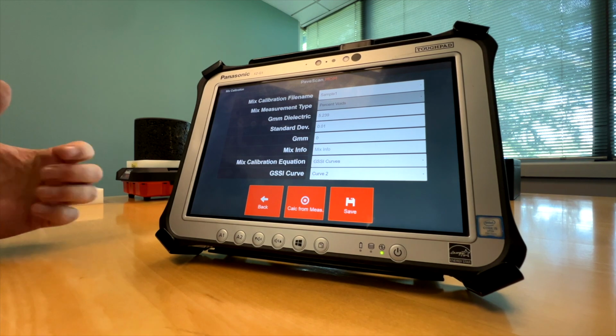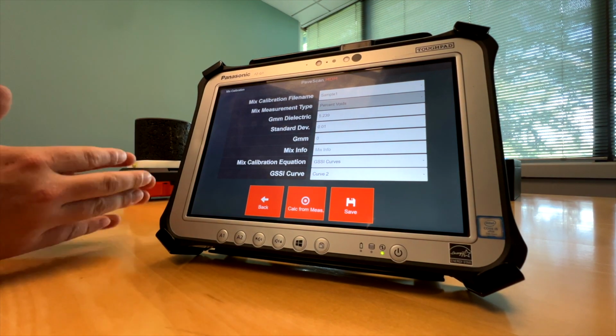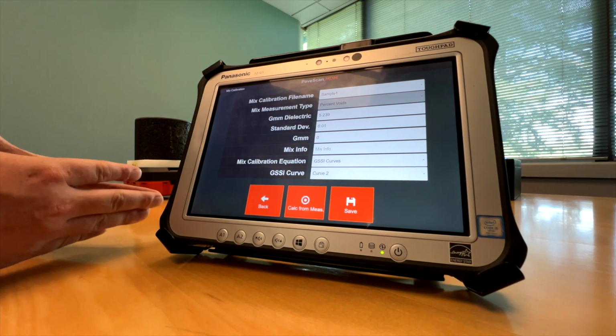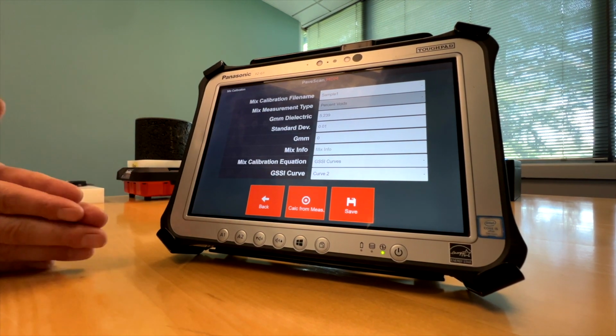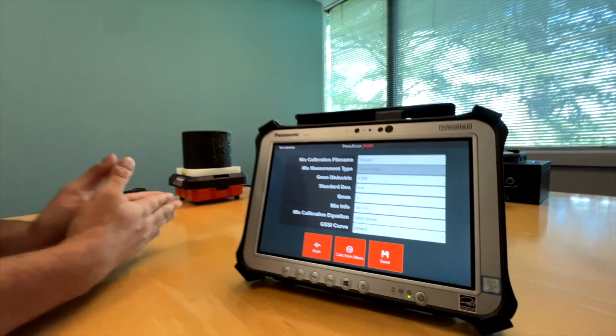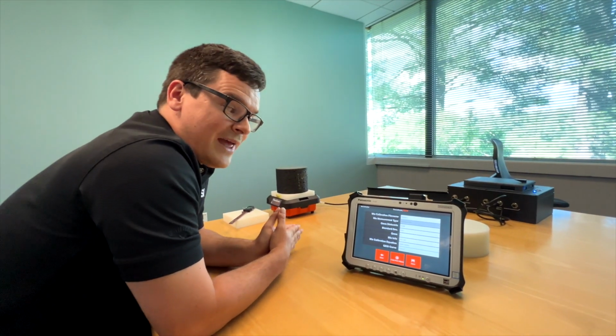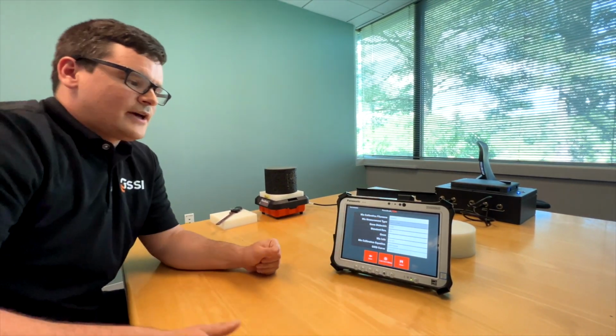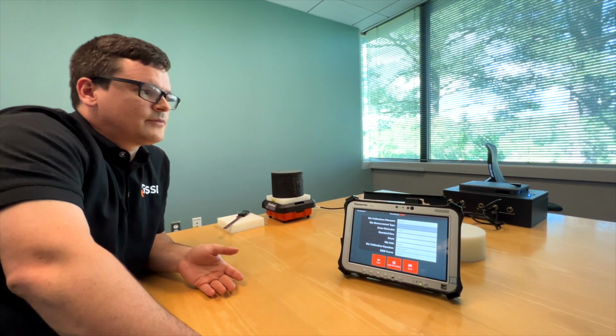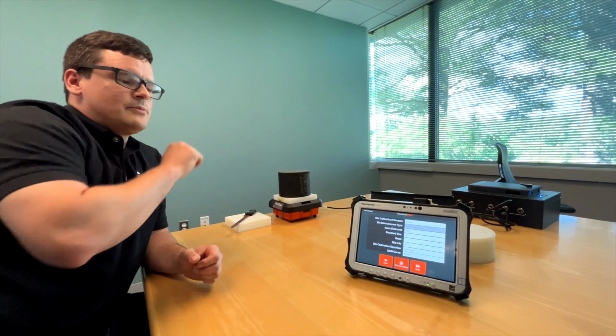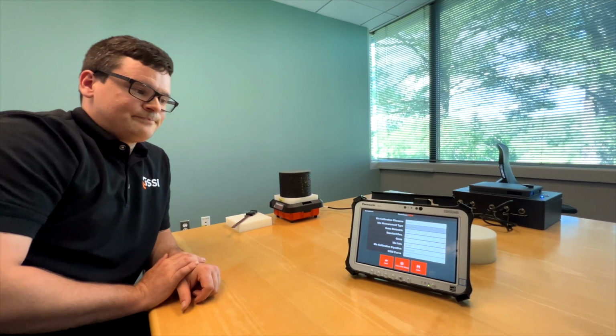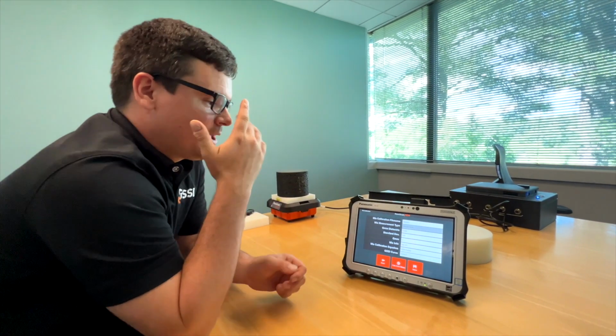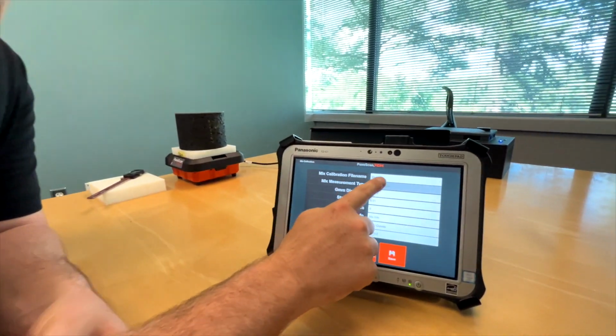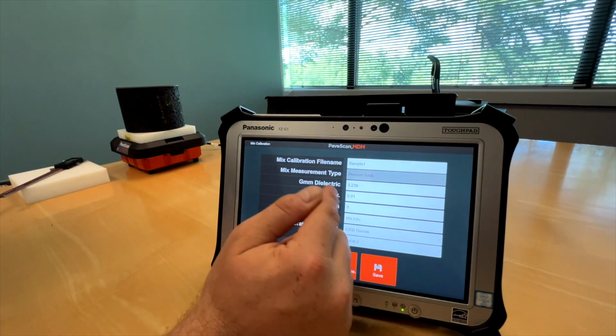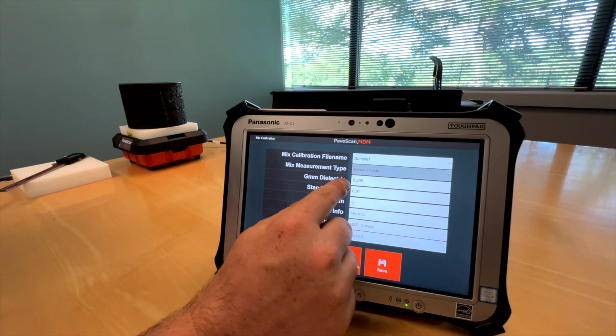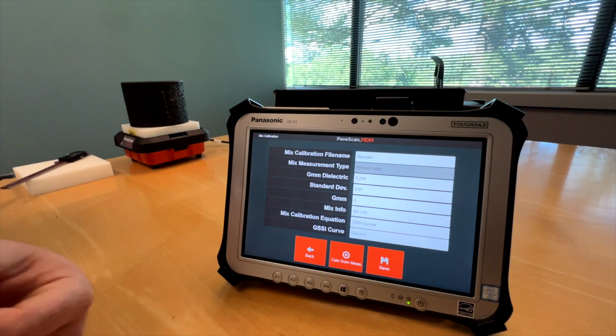Okay. So now I have created a calibration file. I've created a calibration that is linking the percent void, how much air is in a sample, to the dielectric of the sample itself. So now what I can do is I can take that value, 5.239, and if I have something like a PaveScan, I can create a mixed calibration now on the PaveScan. All I have to do is go into the PaveScan, into mixed calibration, create a file name, I could call it whatever I want, and then I only have to enter in the GMM dielectric value, 5.239.